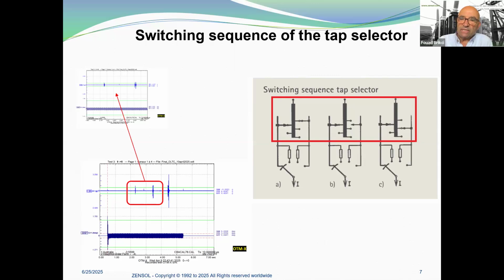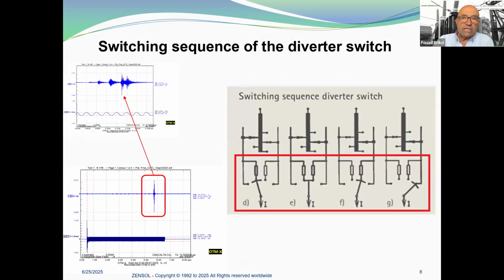So you can see the vibroacoustic recording of the 2 impacts produced by the tap selector. On the top, a zoom of the two impacts. On the bottom of this recording, this is the motor current. Then the switching sequence of the diverter switch. The diverter switch transfers the load current from the tap in operation to the pre-selected tap. So you can see the impact produced by the diverter and the zoom of the impact. Here on the bottom, the diverter transition, and here is the zoom of the graphics.